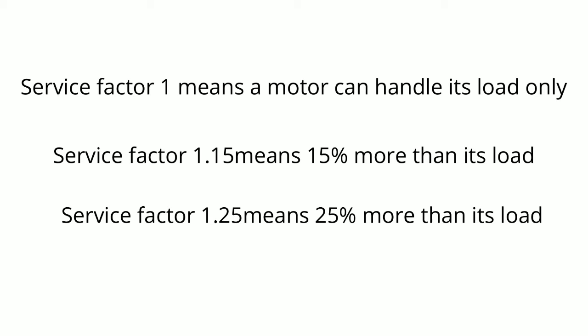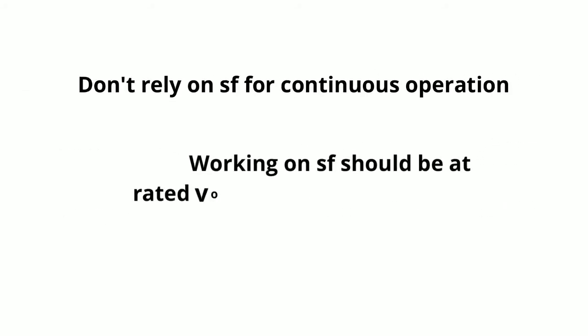You may come across a motor with service factor up to 1.5. It's worth mentioning that a motor lifetime decreases by the increase of the load. Never rely on the motor service factor to handle loads larger than motor rated power for long periods.